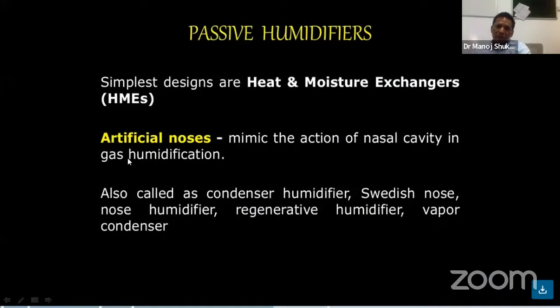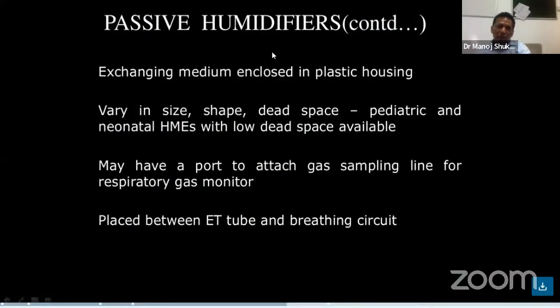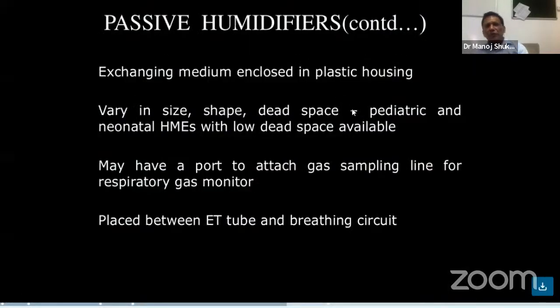Passive humidifiers are the simplest design and are called heat and moisture exchangers (HME). Also called condenser humidifiers or regenerative humidifiers, these are used in our OT and ICU setups on a regular basis. This passive humidifier uses an exchange mechanism enclosed in plastic housing of various sizes. Dead space and neonatal HME with low dead space are available. It may have a port to connect to the gas sampling line for respiratory gas monitoring. It is placed between the ETT and the breathing circuit.